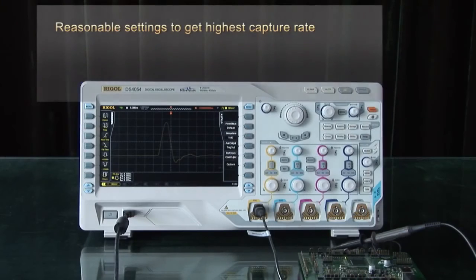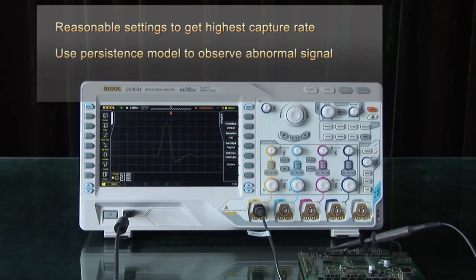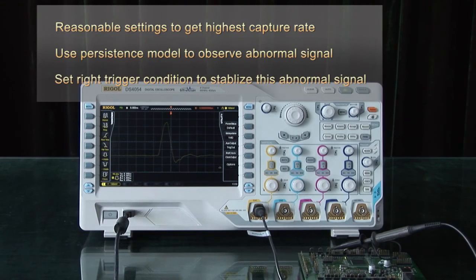The key points are: use reasonable settings to get the highest capture rate, use the persistence mode to observe any abnormal signals that may happen very quickly or at short intervals, and set the right trigger condition to stabilize the abnormal signal. Thank you.